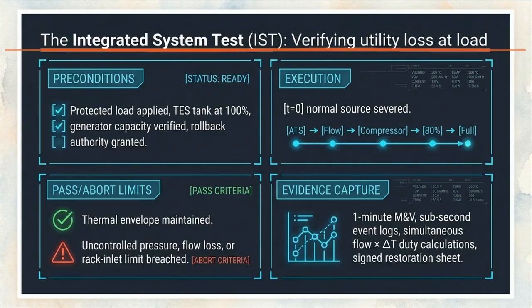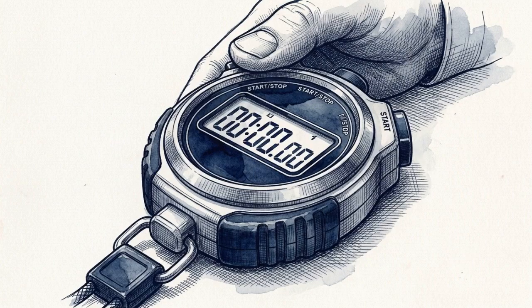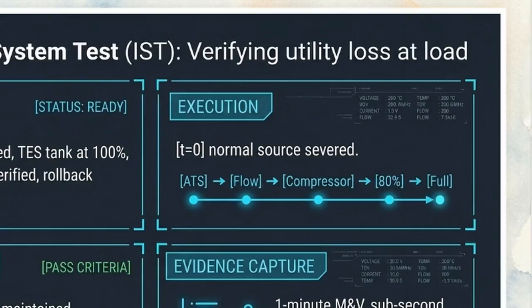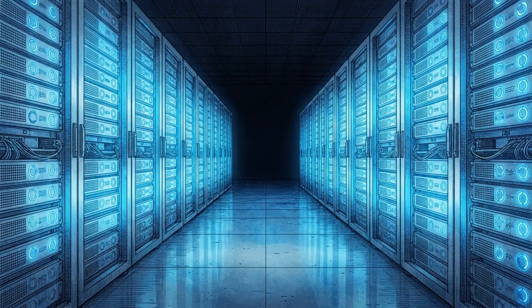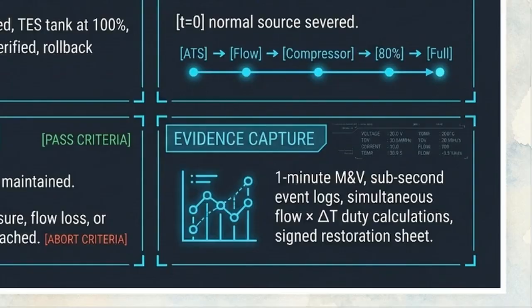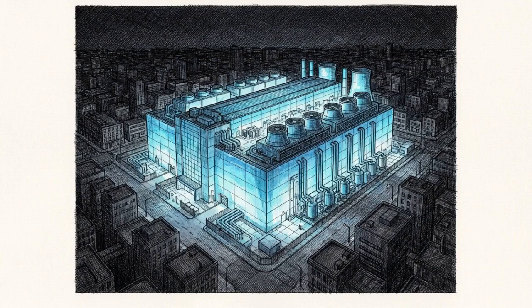This Integrated System Test dashboard shows exactly what is tracked during the blackout simulation. The execution tracks a strict chain of verified events. It logs the exact second the automatic transfer switch engages, the proof of flow, the first compressor firing, the plant crossing the 80% capacity mark, and the final achievement of full duty. The pass criteria are absolute. The data hall's thermal envelope must be maintained for the entire duration without triggering uncontrolled pressure spikes or losing flow. The evidence capture proves this by logging the simultaneous flow and temperature calculations minute by minute. The integrated system test forces the facility to prove its theoretical design margins can actually survive the physical, chaotic reality of a total power loss.